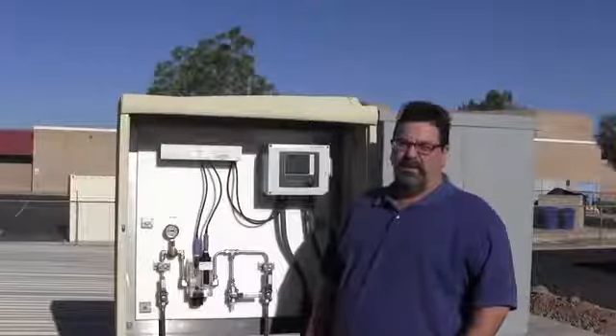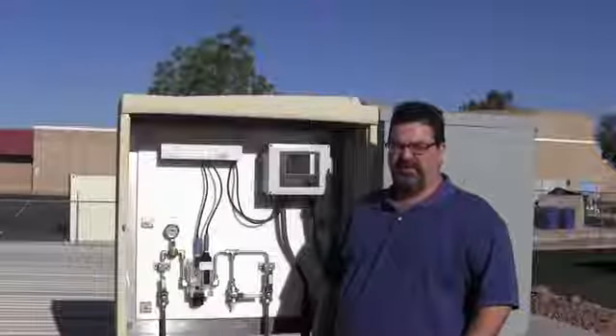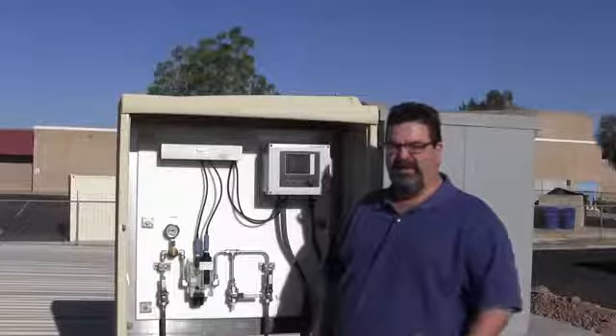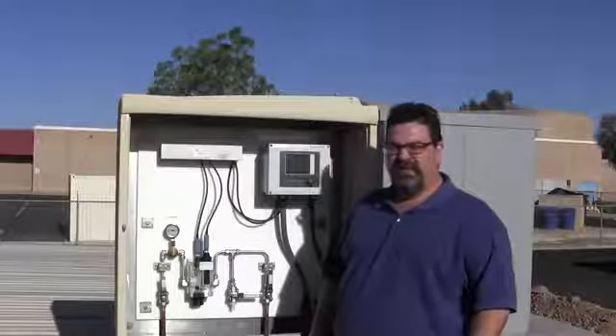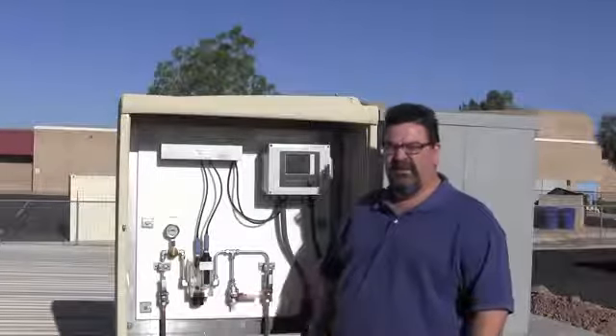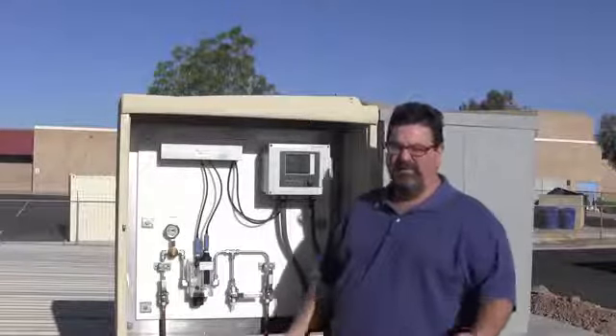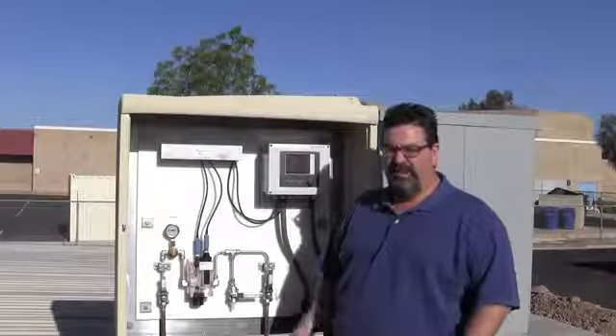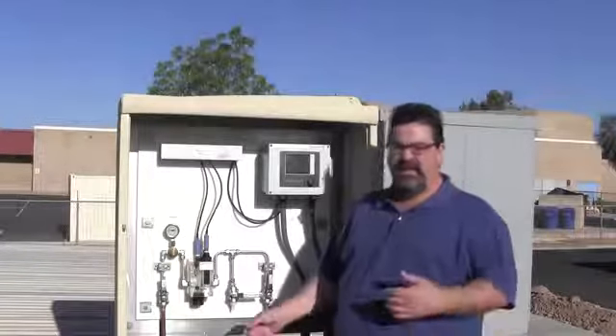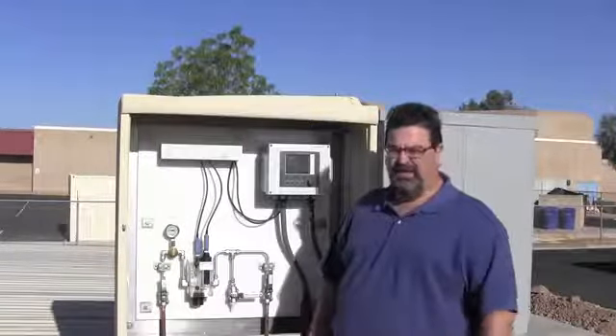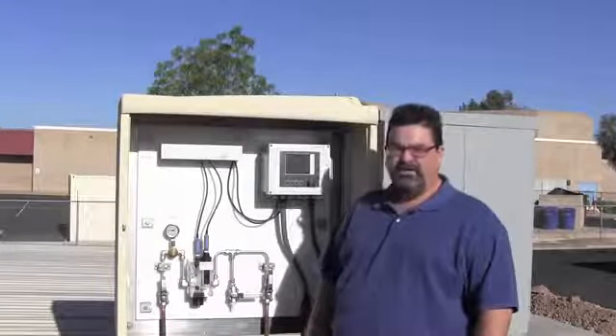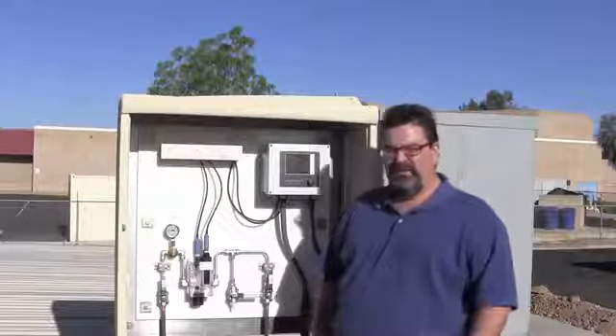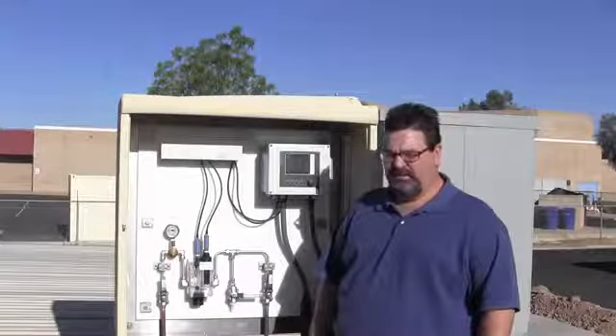You're on. There are two types of calibration for the Endress-Hauser residual chlorine analyzer. The first type is a standard calibration of the chlorine sensor. This would be part of a weekly or even daily maintenance process. The second calibration would be calibration of the pH electrode. We want to cover for a couple minutes the steps in calibrating the chlorine sensor.